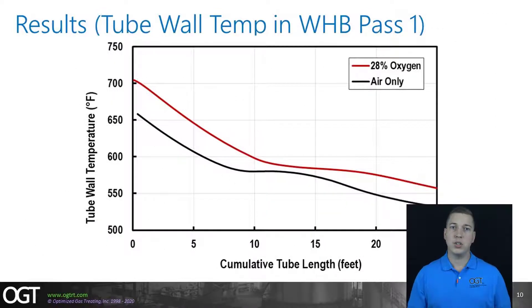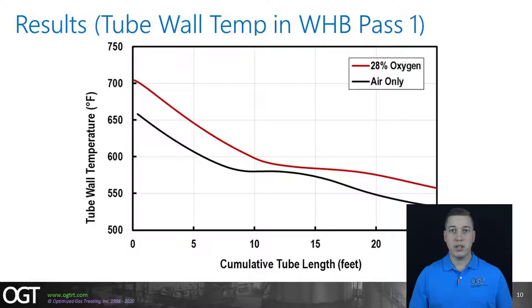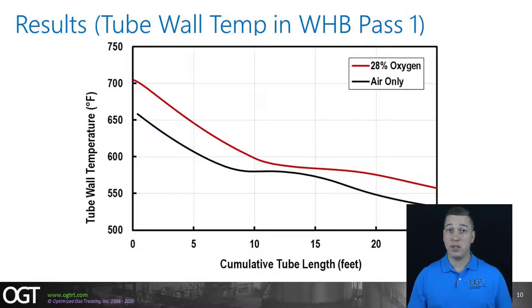This graph shows two curves illustrating how the tube wall temperature varies along the length of the boiler tubes for both the air-only base case and the intended change of 28% oxygen enrichment. It's clear that there is a fairly significant difference between the two cases, especially at the front end of the waste heat boiler at the critical tube-to-tube-sheet joint — the point of maximum tube wall temperature. Even the base case air-only operation is running slightly elevated above the recommended 650°F or 343°C maximum, and this problem is only compounded by the addition of even a small amount of oxygen enrichment.